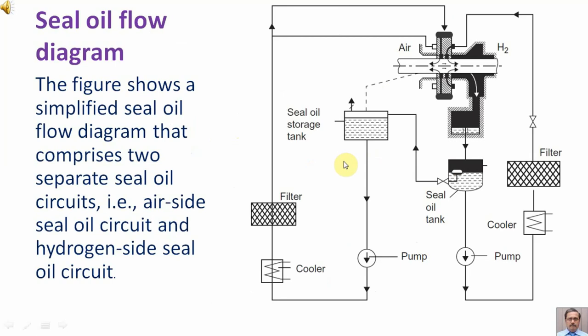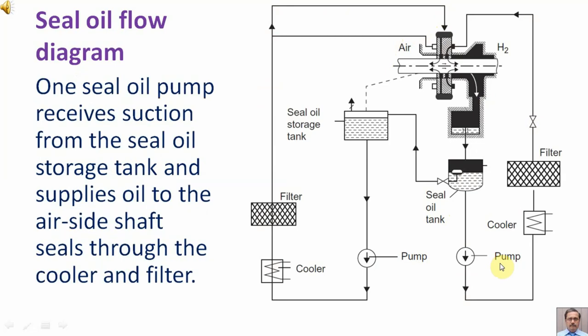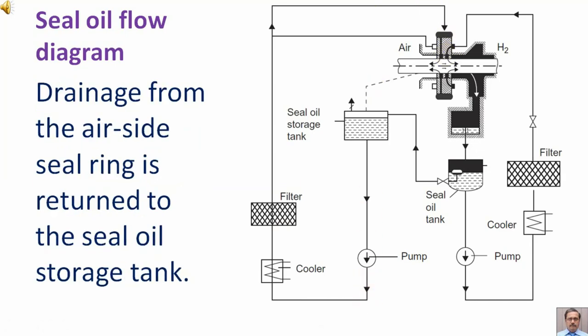One seal oil pump receives suction from the seal oil storage tank and supplies oil through the cooler and filter to the air side shaft seals. Drainage from the air side seal ring is returned to the seal oil storage tank.